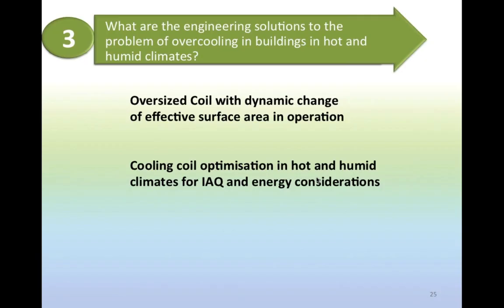Now I want to talk to you a little bit about what's possible. We said increasing the air temperature is not going to work by itself. We need to relook at what's happening in terms of the other parameters. So what can we really do? Systems are oversized. So for overcooled buildings, what we really need to do, if only we could change that oversized coil during commissioning, perhaps replace it with a smaller coil, maybe we would have done the job. If only we would have sized the coil correctly, maybe it's not so bad.